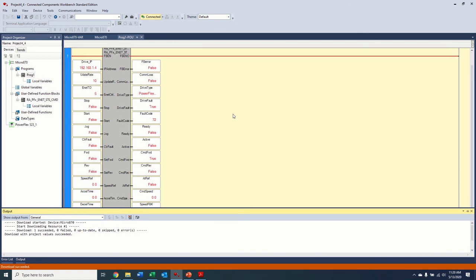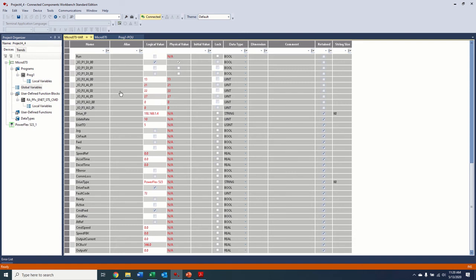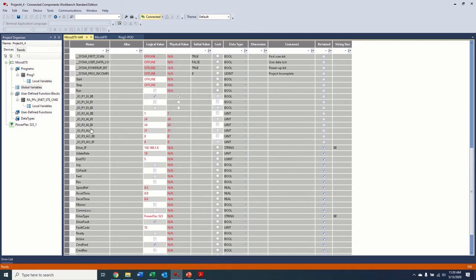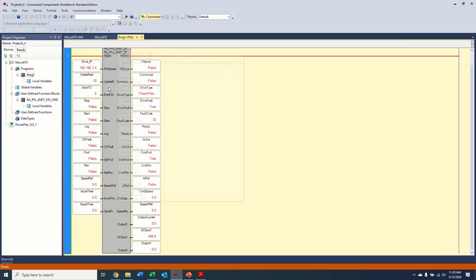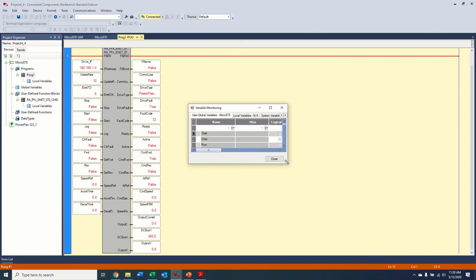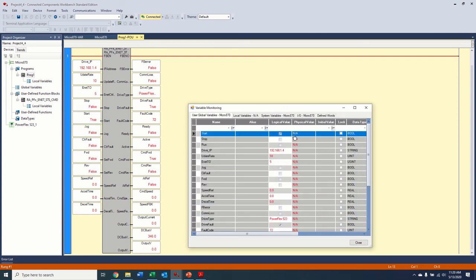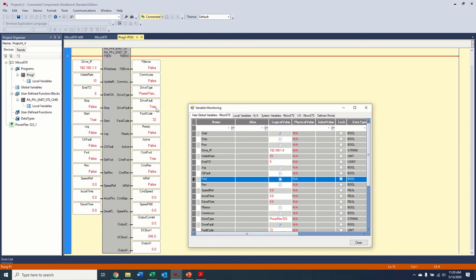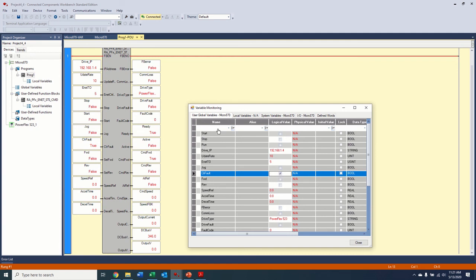Okay. So here is our drive block. Again, we're getting all this information into these tags now. If we wanted to, and I created these as global variables so that we can pull them out throughout any program. You can create them as local variables if you're just using them inside that program, just like Logix. But you can see we have all our values in here. What I want to do is come in and give us a start command here. So if we issue a start, it's not going to start. You know why? Because we have a fault on the drive. So we have to take that away. Issue a stop just to make sure that we are stopped. And we're going to come in and clear our fault.